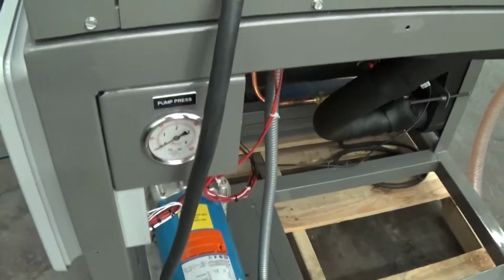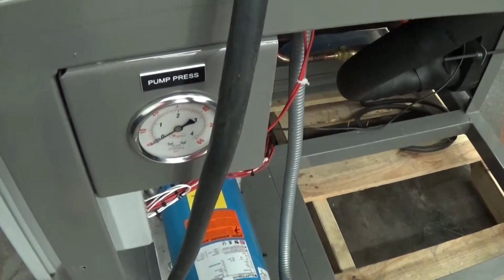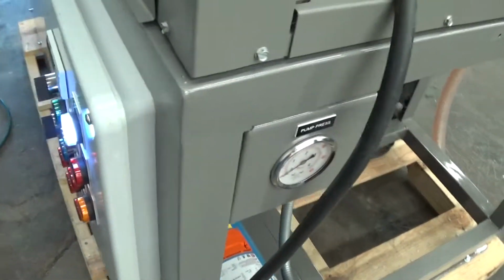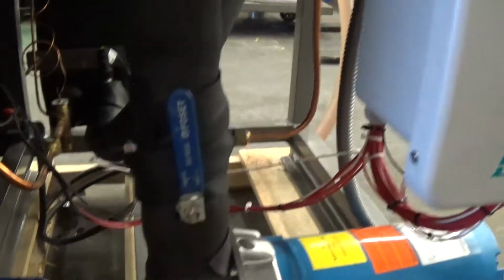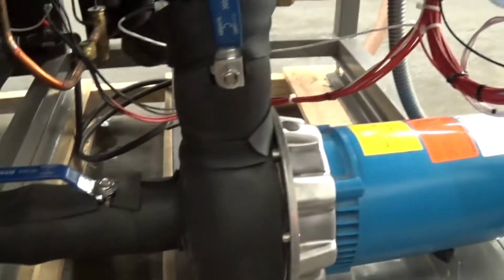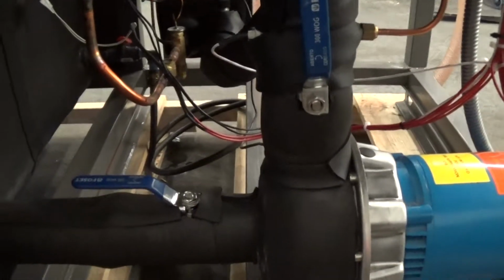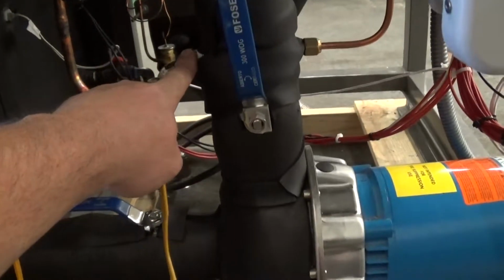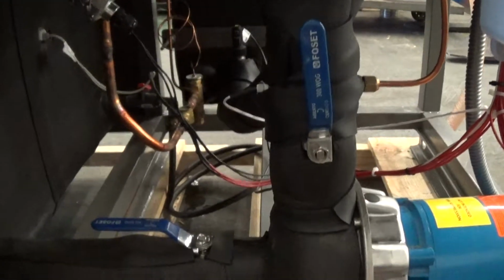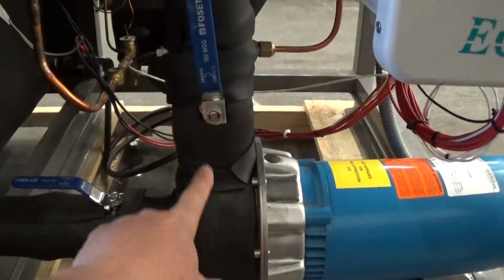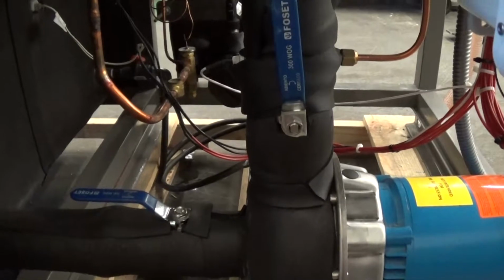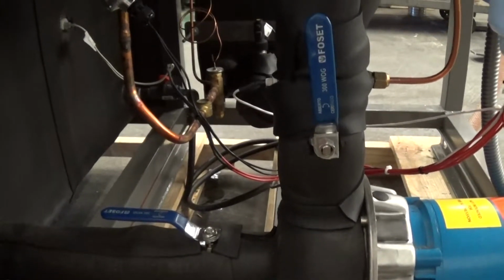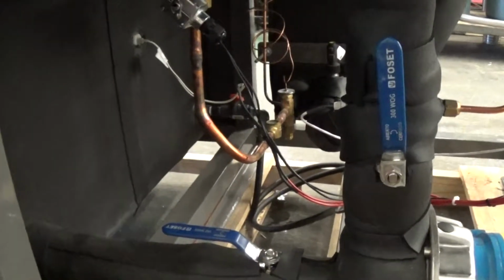And here we have our water pump pressure gauge too. We do have these shutoffs here at the pump. They both ship in the open position, should be left in the open position. Here is our temperature sensor. We're actually sensing the temperature of the fluid discharging out of the pump. So effectively, we're sensing the tank temperature.